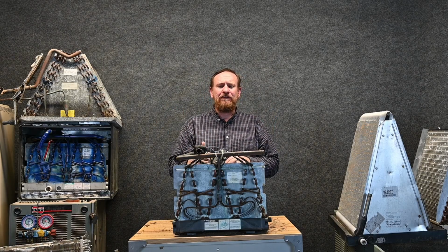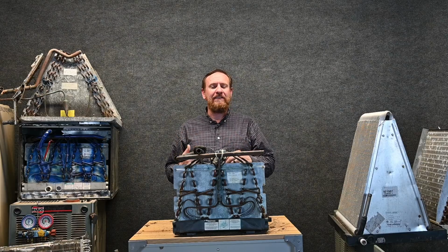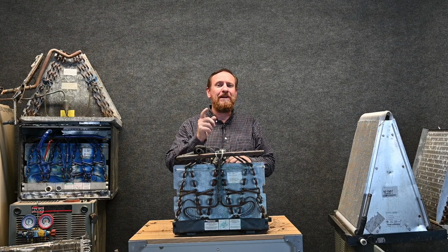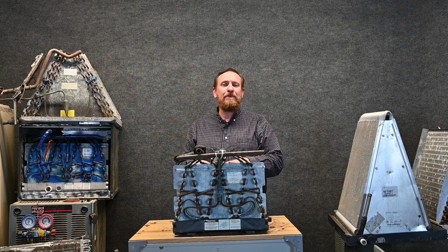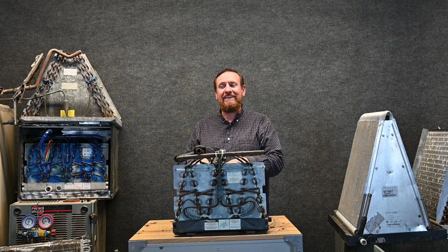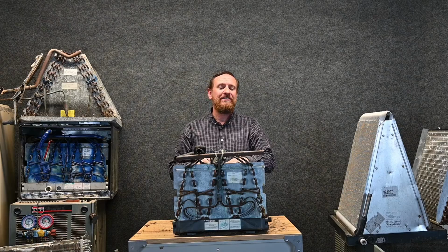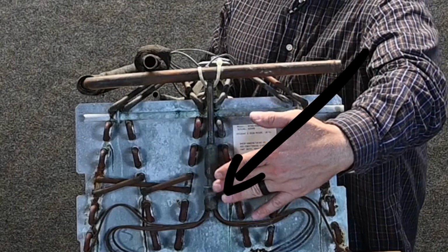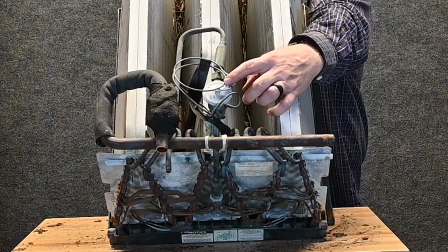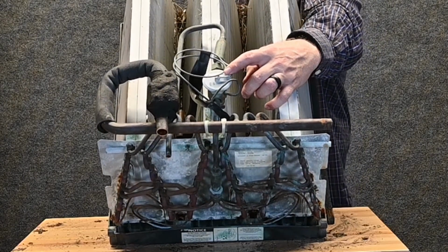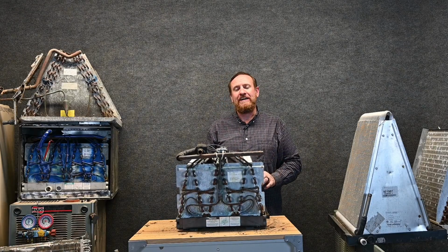So a lot of times, if I have to do a true coil clean where I pull it out and clean it up, if it does have a capillary tube, I'll replace it with a TXV. Now in this case, anytime you open the system up, you want to look at the metering device, and at the outdoor unit, write what kind of metering device it is. And this one, it's a little tricky. It looks like a fixed orifice right here, but in reality, we have a thermostatic expansion valve in this guy. So we need to take that into account, so outside I write TXV.